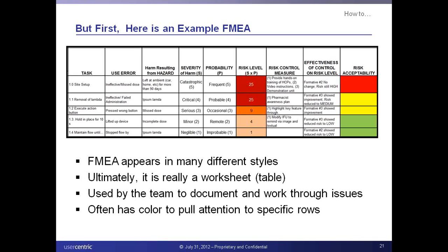The purpose behind this is to have a strong document that covers and anticipates as many problems and hazards as you can imagine, then assesses the risk level associated with it and comes up with risk measures. Because when you identify a potential hazard, you want to come up with a risk control, some way to mitigate or eliminate it. This is where we talk about design changes, ways to make the design smarter so the hazard can be assessed for how effective the control is, and ultimately tell you how safe or how risky your product is.